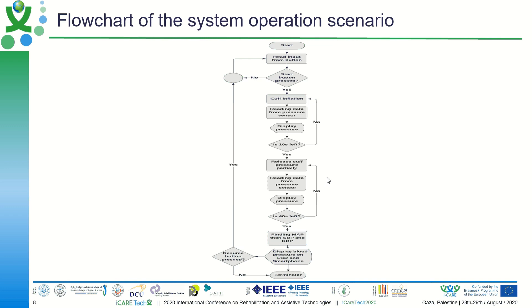This is the flowchart of the system operation scenario. First, we have a button for taking measurements. Once this button is pressed, we start the cuff inflation. We then read measurements for about 10 seconds, then release and deflate the cuff. We take measurements again and process this data to extract what is called mean arterial pressure, then display this value on the LCD display, and keep looping in the program.